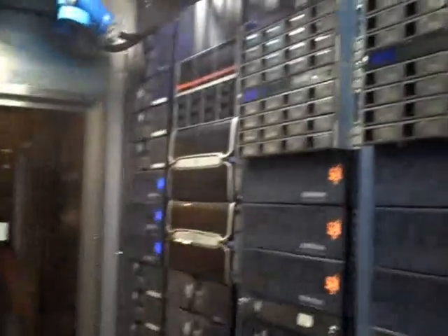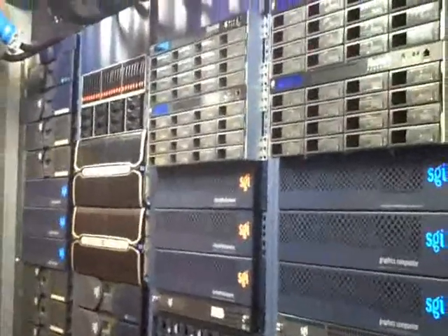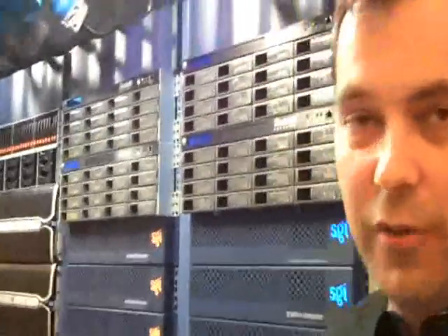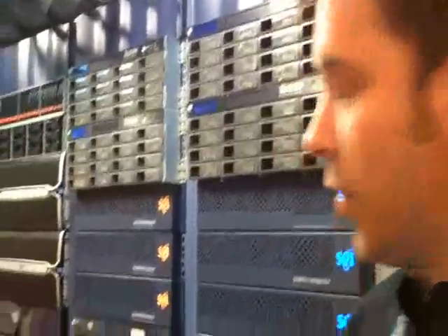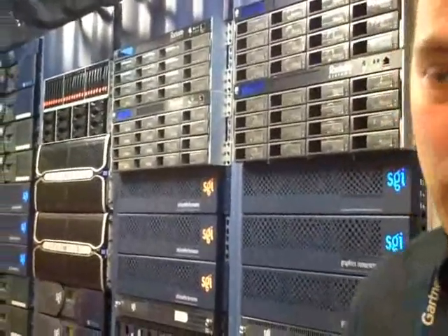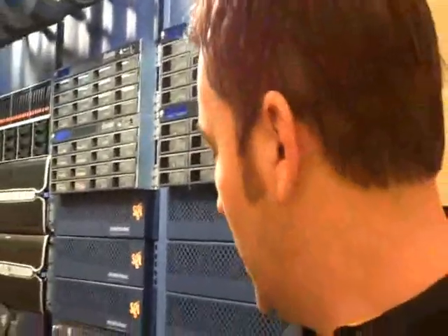So the racks that are here, the four post racks, you can also get the unit without racks. It comes off the shelf empty, and you can wheel in your own racks right off the data center floor. Or you can purchase the four-post racks, and we are vendor neutral, so it allows you to rack and stack your own servers in the unit. So you can start with four, get that going, and expand out to 16.